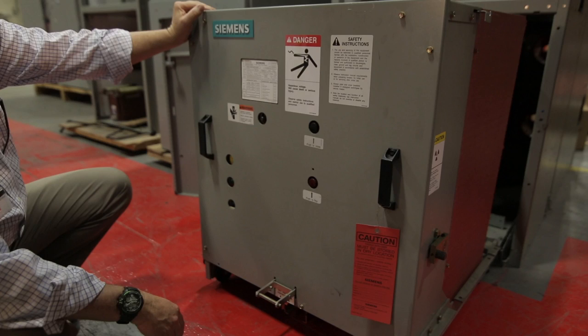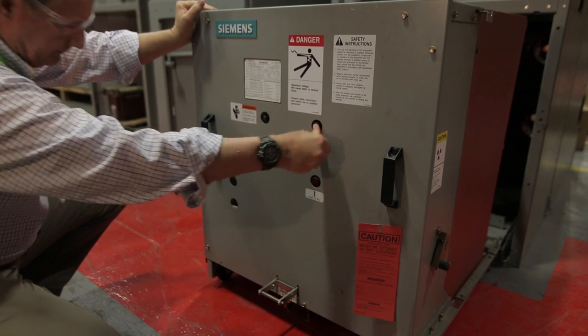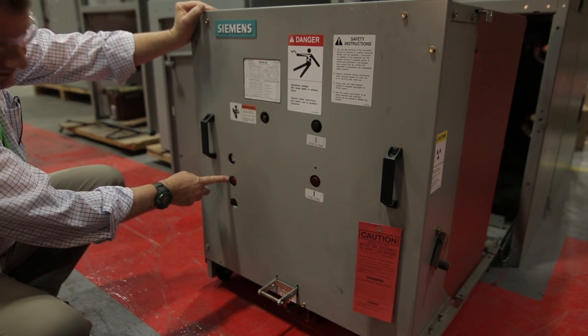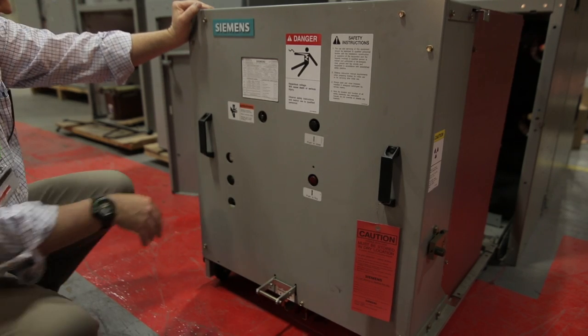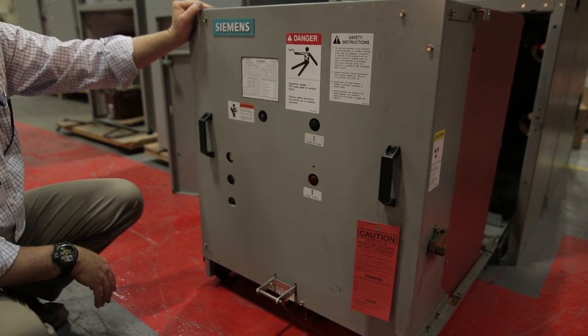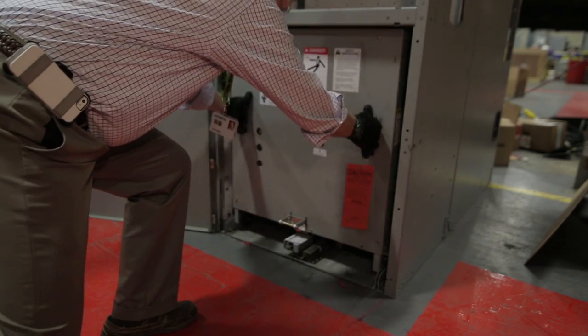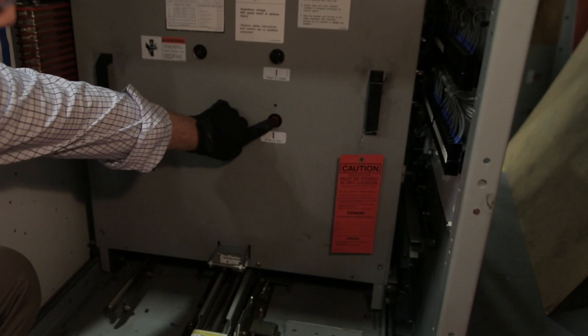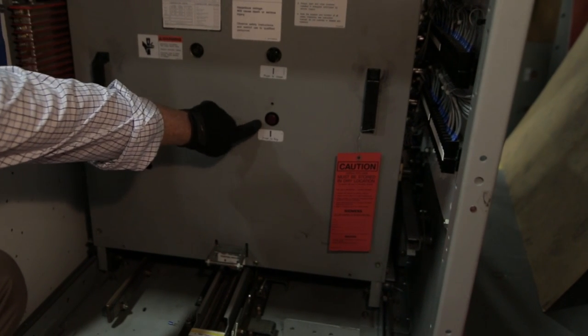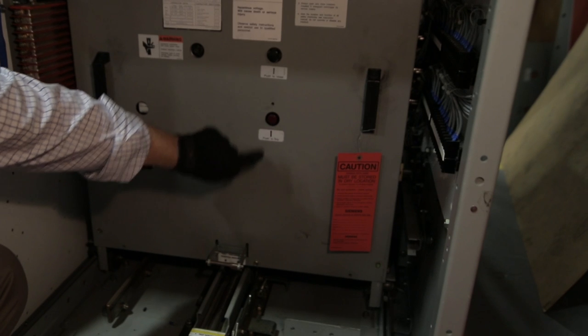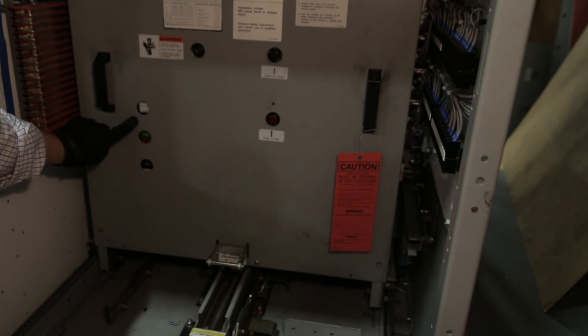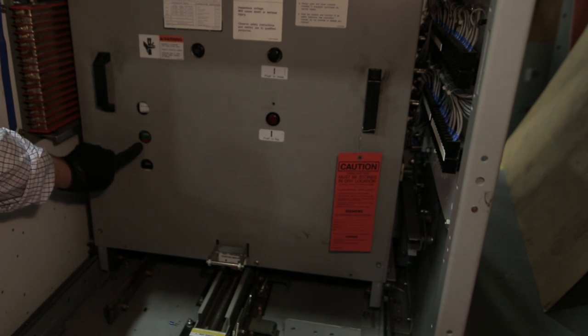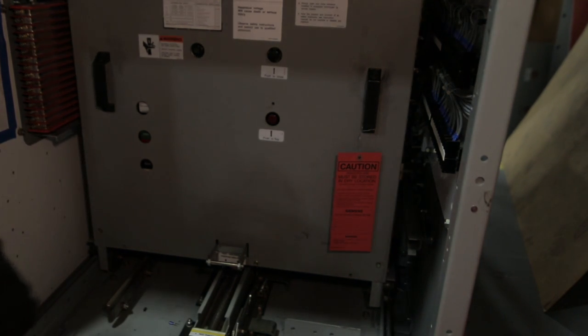Next, we're going to demonstrate the spring discharge check procedure. Perform the spring discharge check before removing the circuit breaker from the pallet or switchgear. The spring discharge check should be performed after de-energizing control power. This check assures both the tripping and closing springs are fully discharged. Open the circuit breaker and rack to the disconnect position and then perform the spring discharge check. Press the red trip push button and then press the black close push button. Press the red trip push button again. Verify the spring condition indicator shows discharged and then verify that the main contact status indicator shows open.